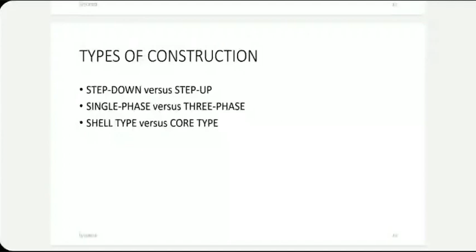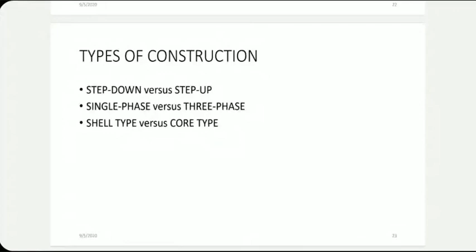For each phase, there will be one primary, one secondary. So there will be three primary windings and three secondary windings, wound generally on the same core, but if necessary, separate cores can also be there. It all depends. So one way to look at transformers is step down versus step up. The other way is single phase versus three phase. And the third method is what we have already seen, shell type versus core type.